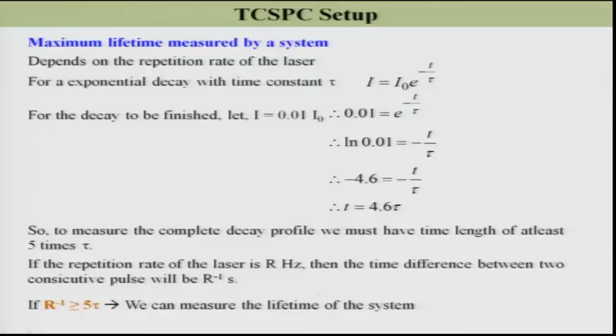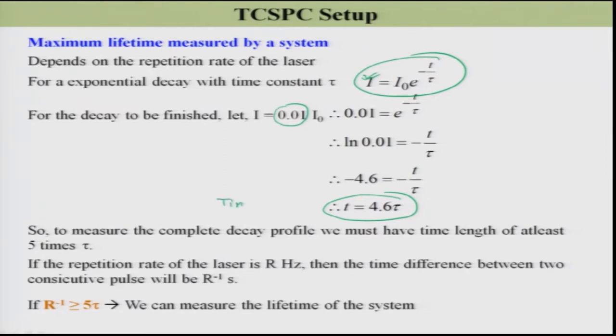If your system undergoes a single exponential decay, the intensity I equals zero only when t equals infinity. But if we consider that I equals 0.01 — just 1% of I_0 — as effectively zero intensity, then you can calculate t equals 4.6 times tau. That means roughly 5 times tau. This T is the time window required to measure the decay. If I have this 5-tau time window, I will be able to measure the fluorescence decay; otherwise not. That is the part of the repetition rate.